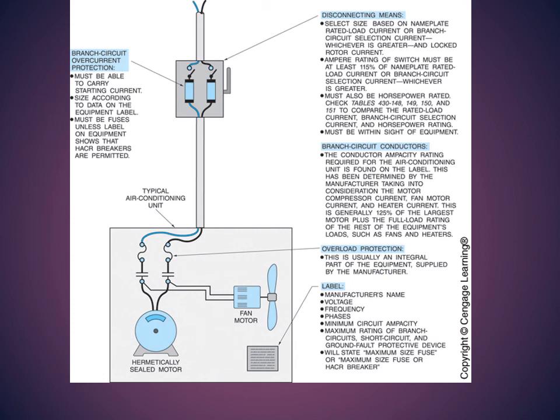Another disconnect switch and a branch circuit over here. And if you notice, again, when we connect or disconnect the power, we want to disconnect both hot and neutral lines. That's the main purpose of the disconnect switch: not only the power but also the neutral. Why is that? In case you have a short in the equipment and there's still some current going through the neutral line, you want to cut that out as well, just to make sure there's no power coming to the equipment and no complete circuit, so you can safely work on the equipment by itself. This is also what's called a nameplate. Every piece of equipment should have a label that gives you the manufacturer name, voltage, frequency, phases, maximum and minimum ratings, and what kind of power is required to supply that equipment to have it run properly.